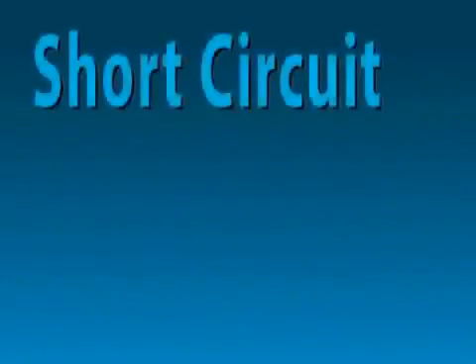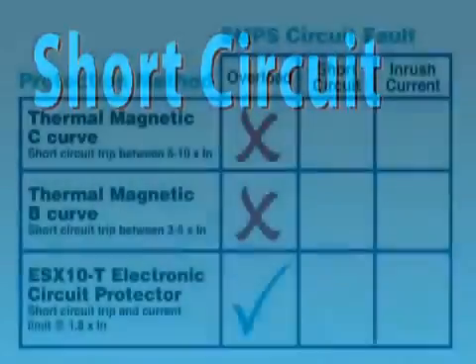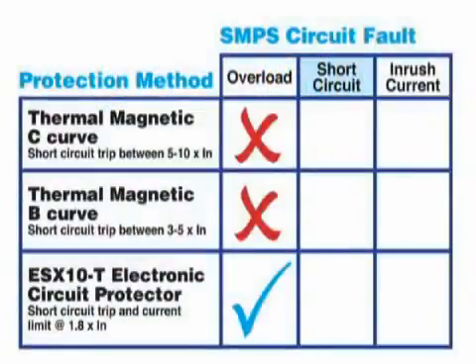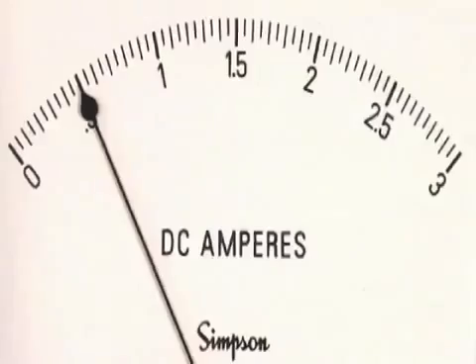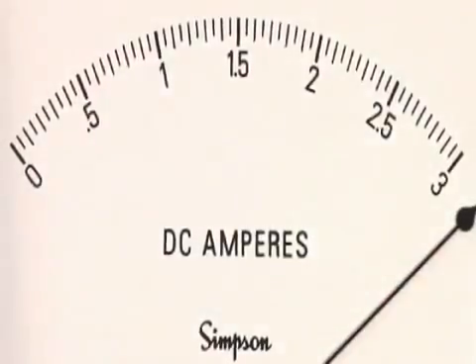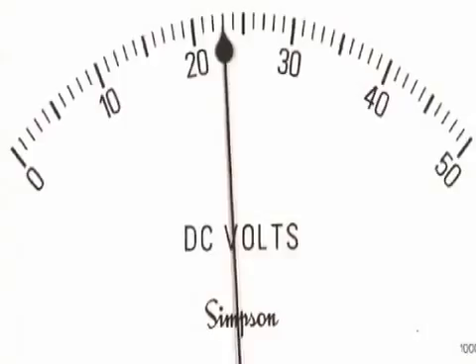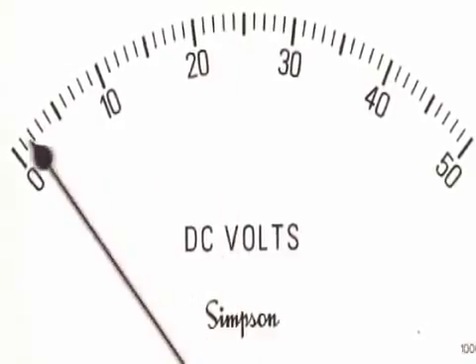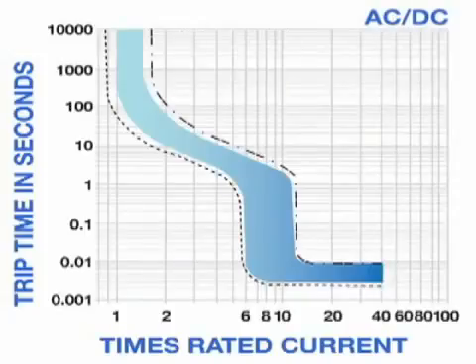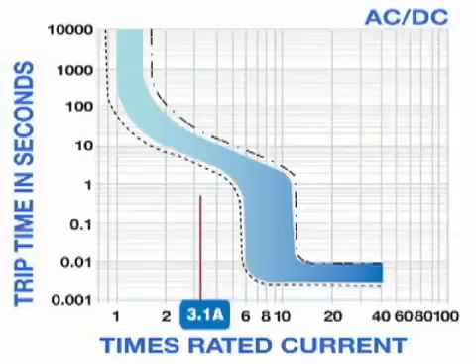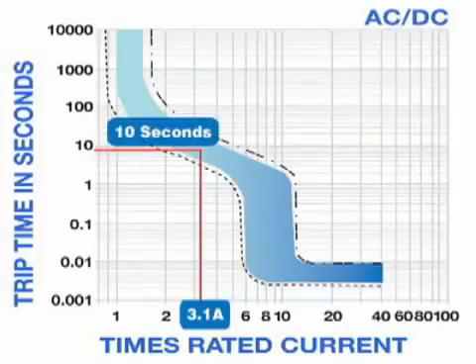Our second condition is a short circuit. Now let's simulate a worst-case short circuit with the 3 types of protection methods. Notice the short circuit current at greater than 3 amps, and the 24-volt DC drops to under 5 volts DC to protect the power supply. The C characteristic circuit breaker did not interrupt the short circuit instantly because it requires at least 6 times the rated current to activate the magnetic trip. In this case, 6 times a 1 amp breaker equals 6 amps needed to trip.